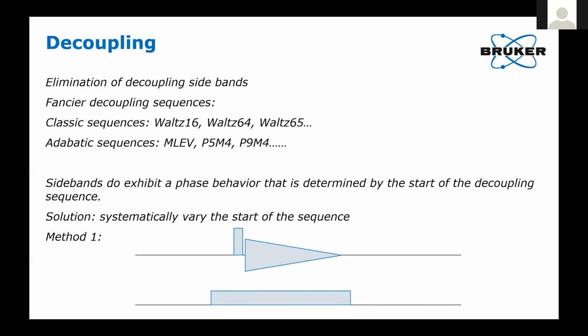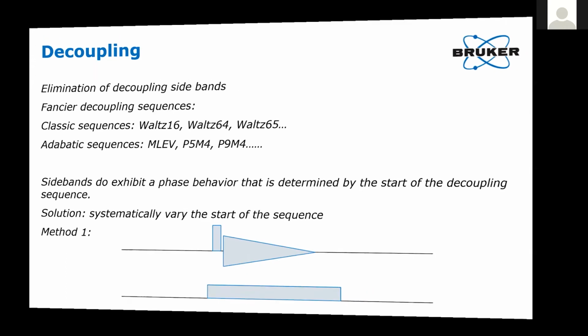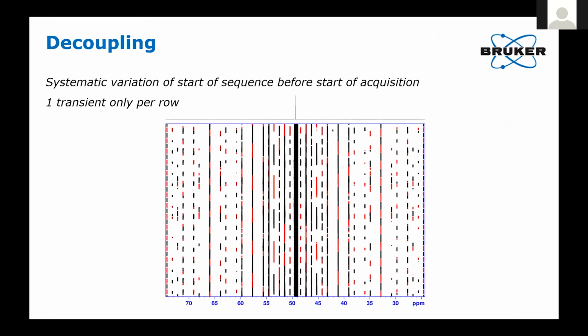So with every scan, you move it a little bit to the left in this diagram, and you accumulate all of these. If you actually look at what happens in an experiment where I do one transient per row, and on each row, I move my decoupler sequence a little bit, you can see all these sidebands here, they change phase, but they change it in different frequencies. And if you do it often enough, you can actually cancel out the decoupler sidebands.